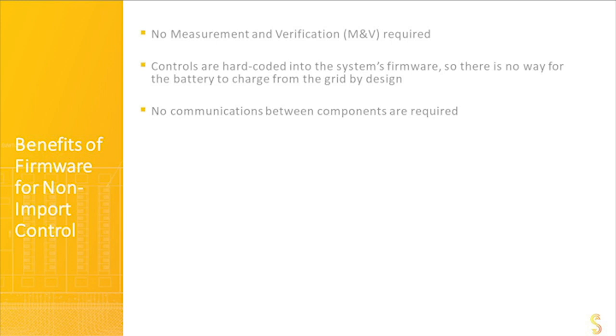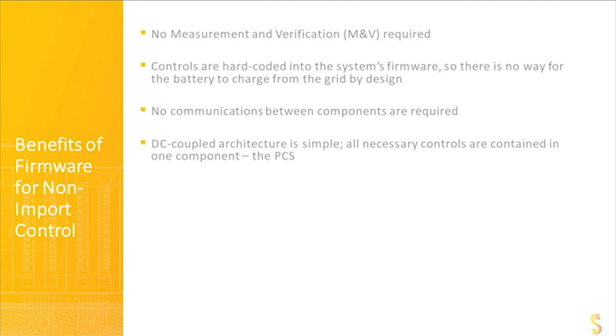No communications. Also, because it's DC coupled, all of this can be hard-coded and built into the inverter, which is very simple to do. This is a software change, or rather a firmware change in the inverter. Relatively simple. You notice it was technology agnostic. We didn't define any particular type of battery chemistry or inverter type or IGBT or anything. This works for any DC coupled solar plus storage system. It's repeatable because you can do this with any number of inverters.